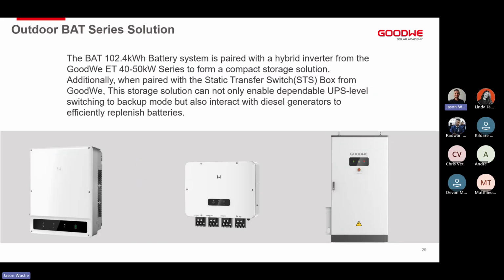So this is just a full solution, what we could see. The BAT 102.4 battery system is paired with our hybrid inverter, which is our ET50, to form a compact storage solution. When we pair it with the STS itself, we are able to achieve UPS level switching to interact with on-grid and off-grid, and then connect our diesel generator if we need to connect a generator as well.